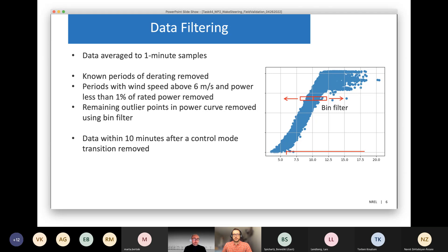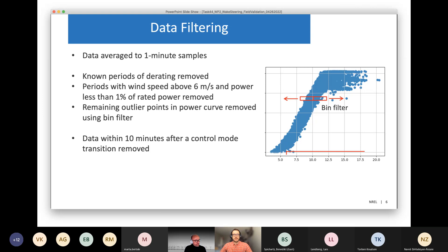We also discard data within 10 minutes after a control mode transition — when we switch from baseline to wake steering or vice versa — to allow for yaw controller transients. The yaw controller is slow because it has to wait until enough error accumulates before yawing the turbine, so we allow for those slow dynamics to adjust to the new yaw offset command.